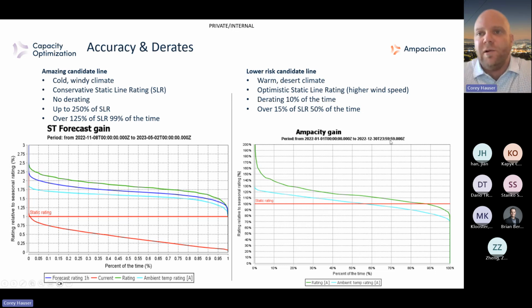So even when you're looking at it here, you're seeing over 15% gain versus static line rating on average, 50% of the time. So when you're talking about having that in a warm desert climate with a non-optimistic static line rating, it's still a great result. But there are going to be times where it derates, and that's just dealt with.